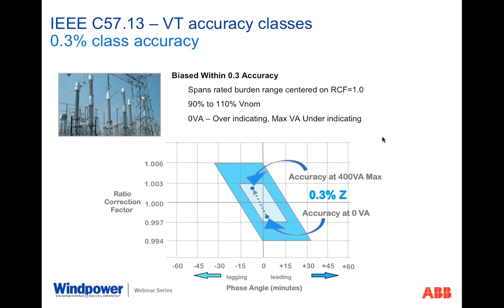We do have voltage measurement devices that we put out there to be able to capture the power requirements by measuring the voltage component. Now, I have to say that voltage transformers provided in the 0.3 class really span a variety of accuracy points. If you look at a typical voltage transformer, we as a manufacturer bias that voltage transformer to start in the 0.3 parallelogram, or the 0.3 class, at the bottom end at zero burden.